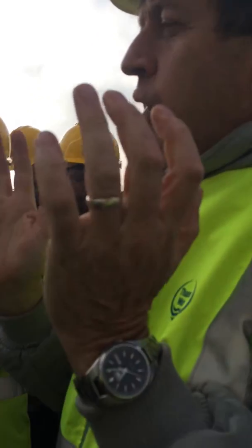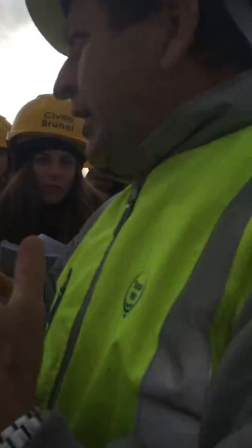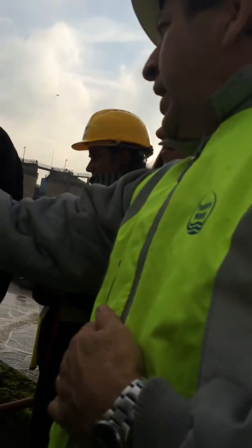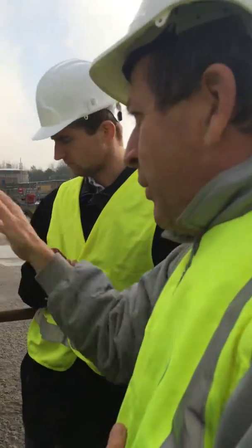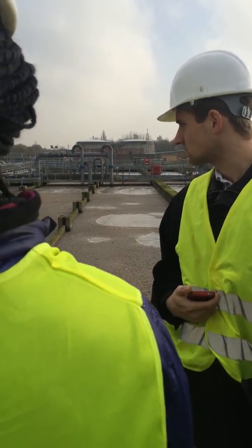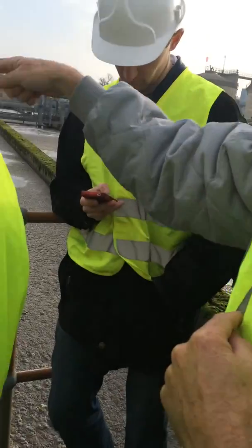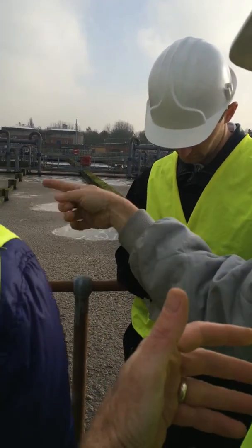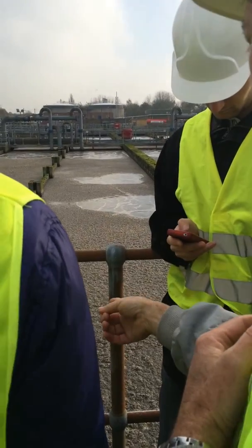So the way we enable that on an activated sludge configuration is that the inlets to each of these lanes we can see on our left here are not aerated. You can see the lanes where we're not adding air, we've got the static surface with scum on the top. Those are anaerobic and anoxic zones. If we think of this whole lane as a single long tank, about 25% of that is not aerated, it's anaerobic or anoxic, and about 75% is, as we can see here, aerated.